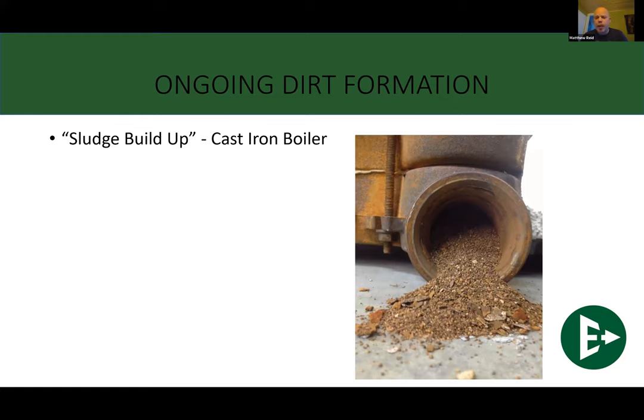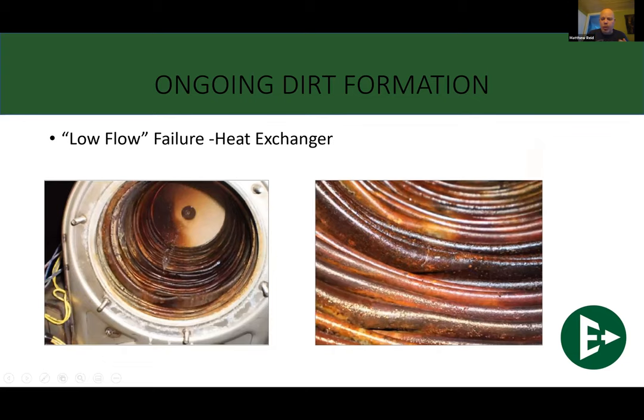They absolutely worked a very, very long time. The difference being the jackets inside of these cast iron units are huge. Lots and lots and lots of room for that scale to build up and that sludge to build up inside of it where you're not having any real impeding on the flow. They're designed actually with that in mind, that they are going to have that build up on the inside of it. So what we want to do is make sure that we limit that as much as we can. Because nowadays, we don't have those big jackets anymore to hold that sludge inside of it. Now we're very tight heat exchangers.